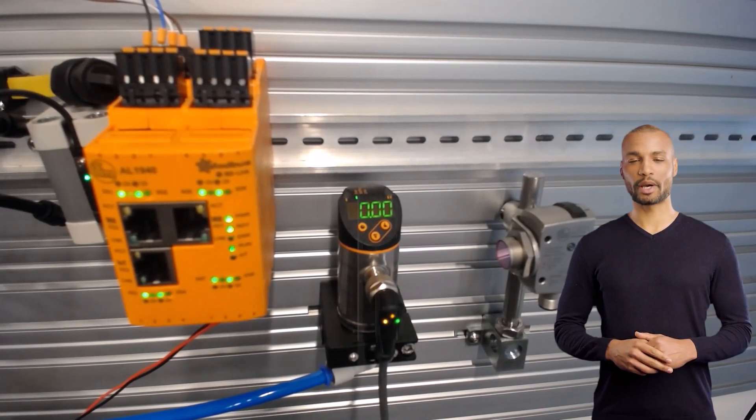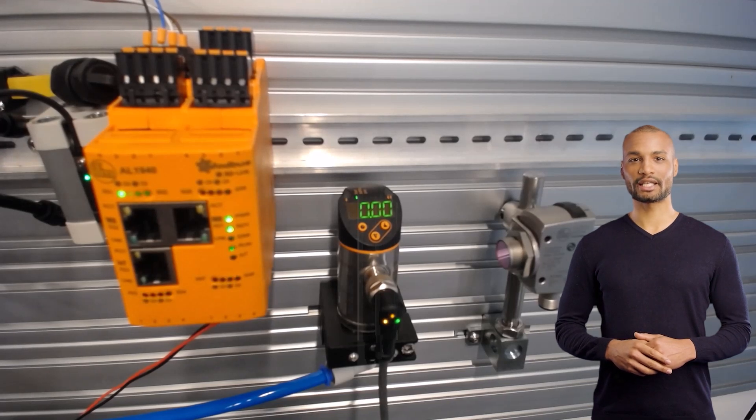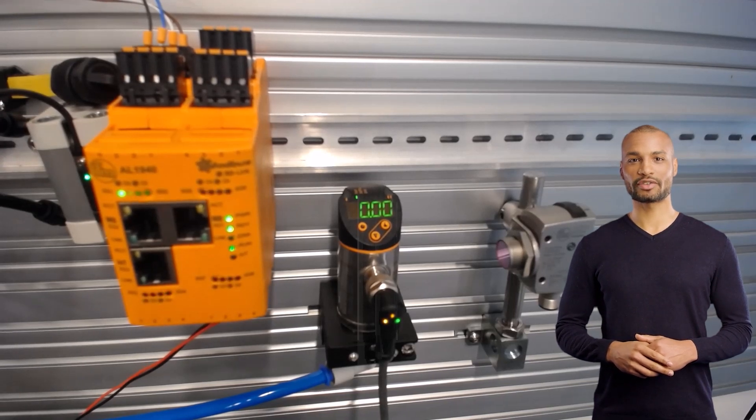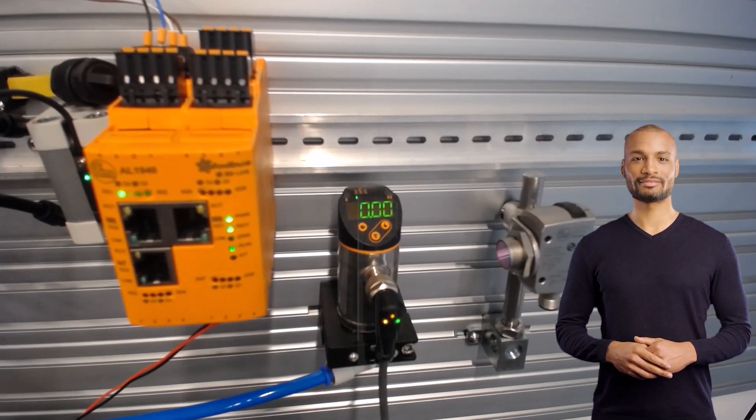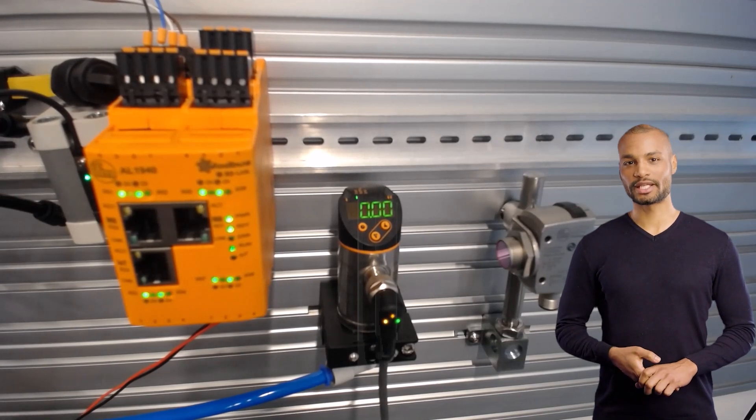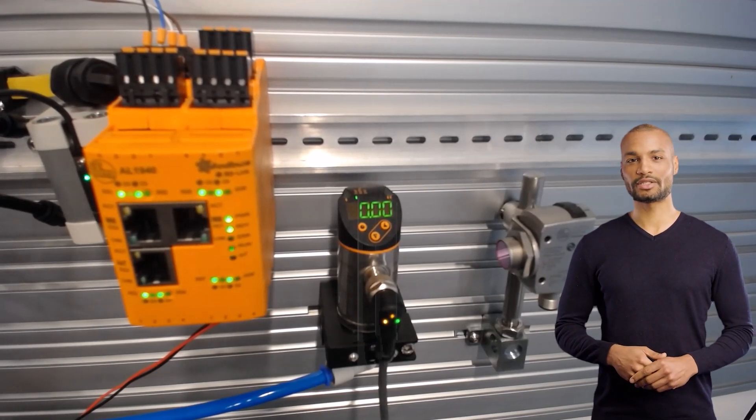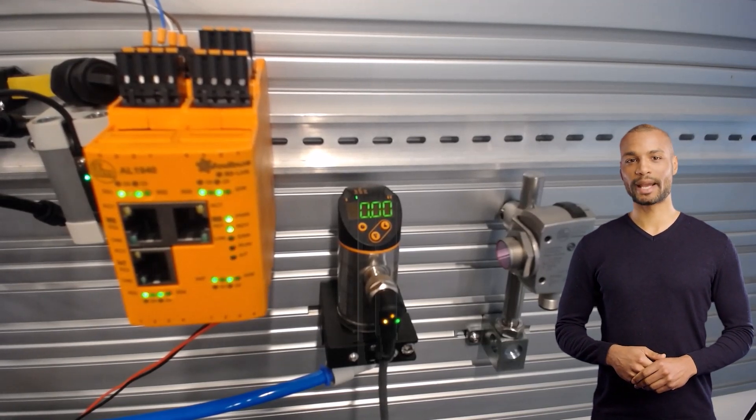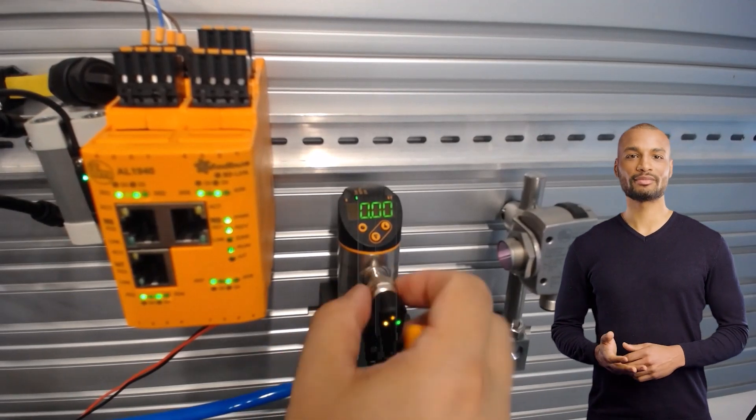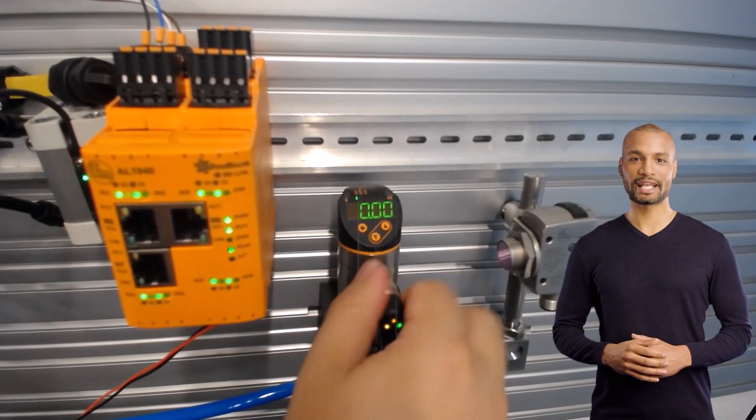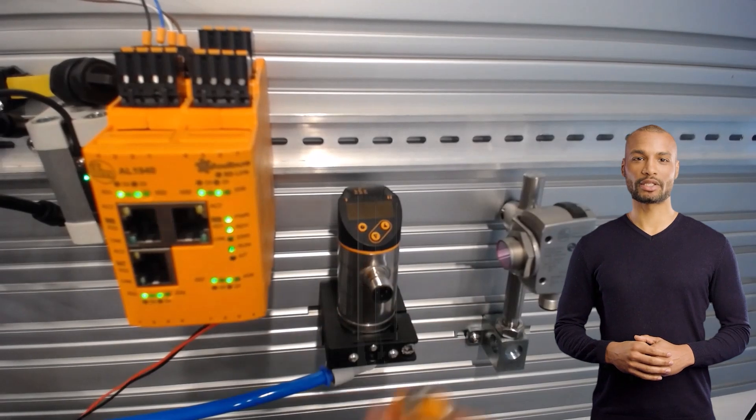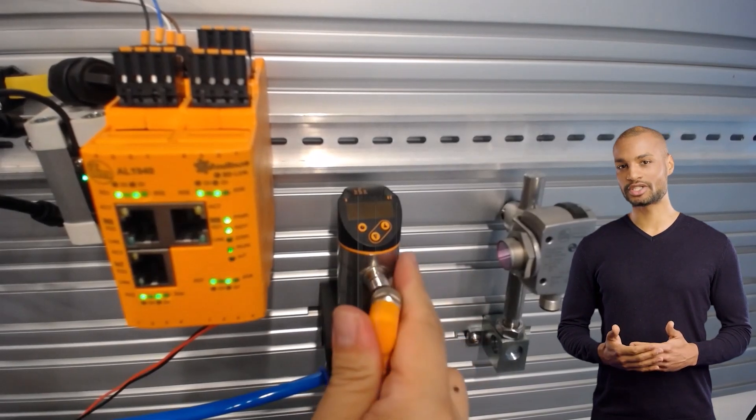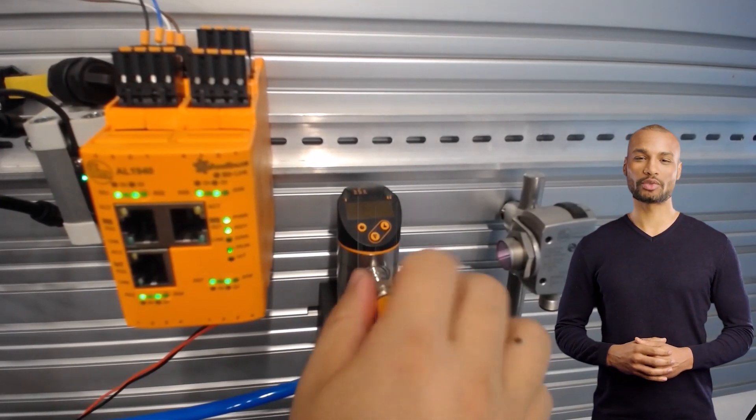Now let's move on to the parameter storage function. As we can see, the current pressure value is displayed in green. This parameter set with a green display is stored in the IO link master due to the backup and restore function. We disconnect the sensor and connect it to a separate power supply without connection to the master or the controller.